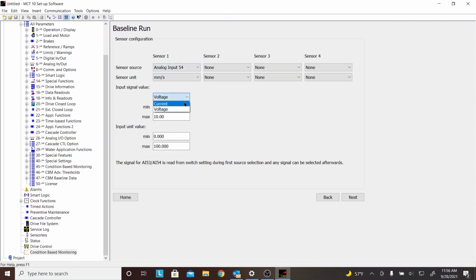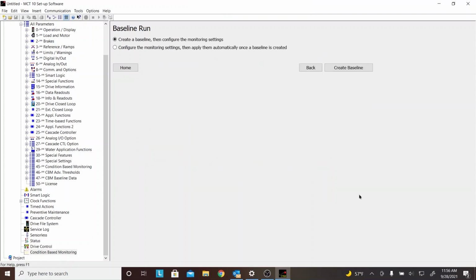So if you had a typical vibration sensor, they're usually 4 to 20 milliamp. They're usually so many millimeters per second. That's where you enter the unit information. But I'm not using that. I'm just using something to fake out the drive for a display. So this is how I've got it set up. Once you set this all up, you go ahead and push next. Now it's going to ask you, let's create the baseline. Finally, this is the heartbeat. We're creating the baseline of a running machine in production that we're going to monitor 24/7.